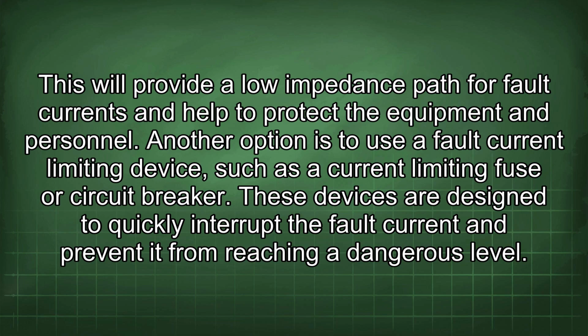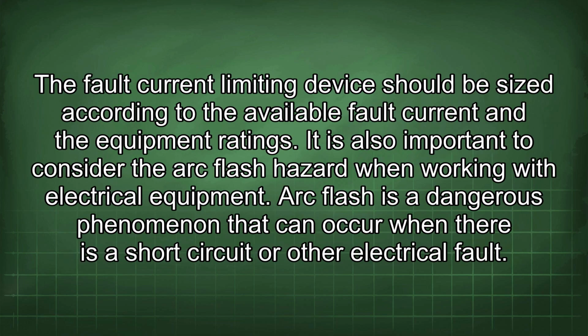Another option is to use a fault current limiting device, such as a current limiting fuse or circuit breaker. These devices are designed to quickly interrupt the fault current and prevent it from reaching a dangerous level. The fault current limiting device should be sized according to the available fault current and the equipment ratings. It is also important to consider the arc flash hazard when working with electrical equipment.